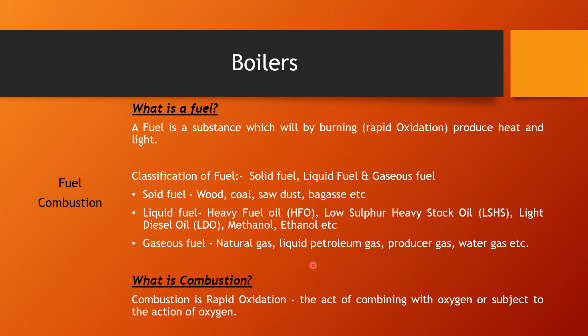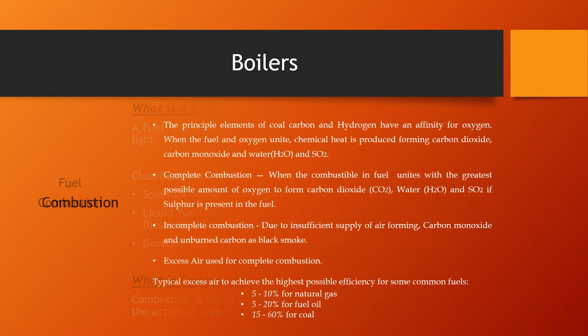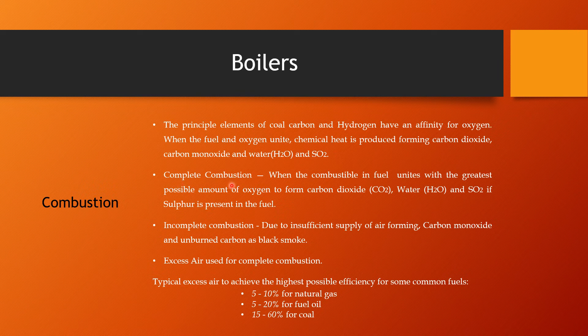When fuel is used in a furnace or boiler, it is called combustion. Combustion is rapid oxidation — the act of combining with oxygen. For combustion, the principal elements of coal — hydrogen and carbon — have an affinity for oxygen. When carbon and hydrogen in any fuel combine with oxygen, chemical heat is produced, forming carbon dioxide, carbon monoxide, water, and sulfur dioxide if sulfur is present in the fuel. Complete combustion occurs when the combustibles in the fuel unite with the greatest possible amount of oxygen to form carbon dioxide, water, and sulfur dioxide if sulfur is present.